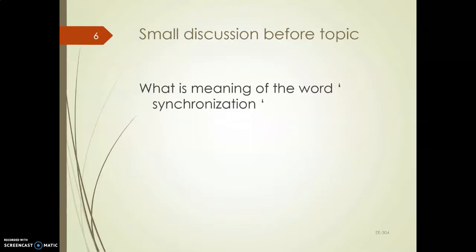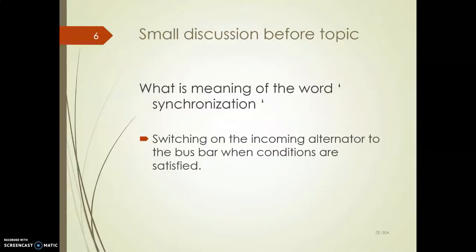We also need to understand what synchronization means. Synchronization means switching on the incoming alternator to the bus bar when all the conditions are satisfied — that is, when voltages, frequencies, and phase sequences are equal. The total process of connecting one alternator to the bus bar under these satisfied conditions is called synchronization.